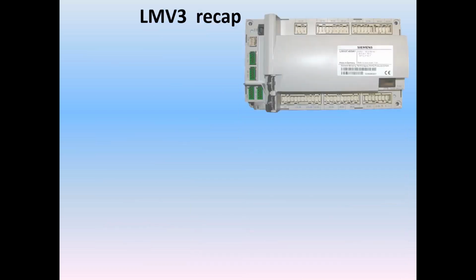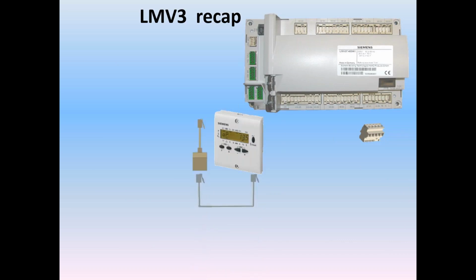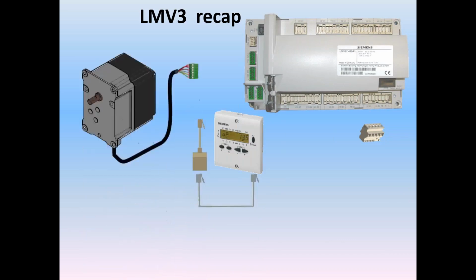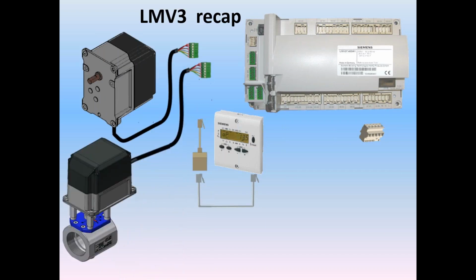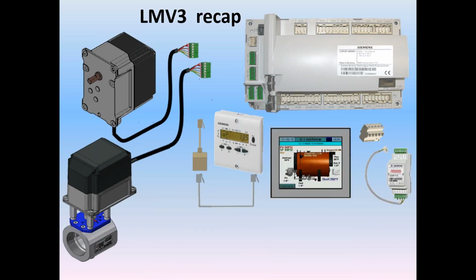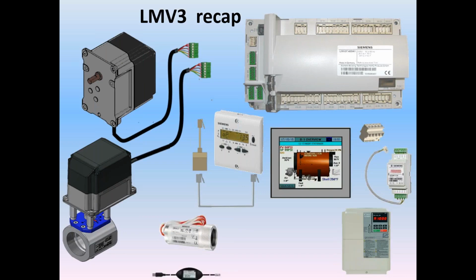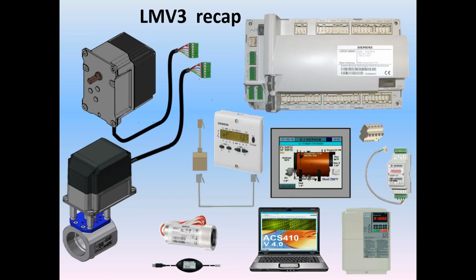As a recap, you have a base LMV3 control, add a terminal set, get terminals in there. An AZL display is highly recommended, and of course the cable to go along with it, the TDC combos. Servos as needed, maybe valve actuator assemblies. You can add OCI for the Modbus support, such as an HMI. Scanner you're going to need, either a flame rod or a UV scanner. A VFD option if you choose to use that. And then the PC would be connected through the OCI dongle that you see shown on there.